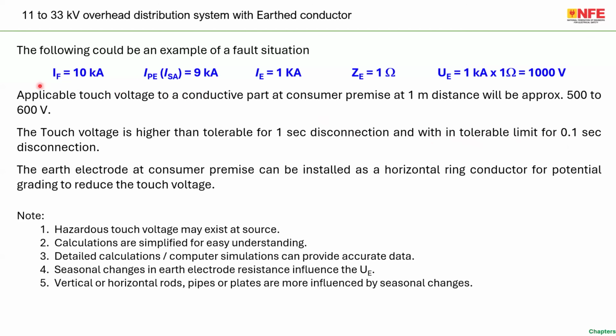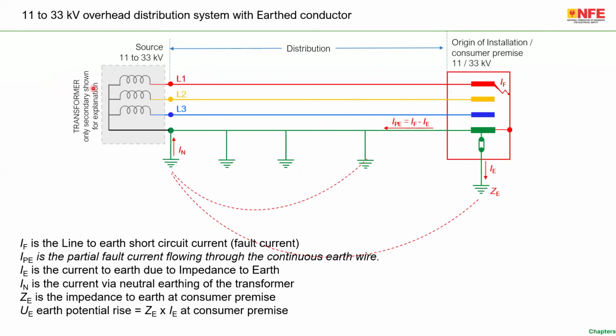But what I wanted to explain to you is, if you are following regulation 18 and regulation 74, the majority of the fault current goes through either the armoring or through the metallic fault return path. Only a very small amount of current flows through the earth electrode. As a result, the earth potential rise is very much under control. The chance of people getting a shock is very much under control, very much limited.